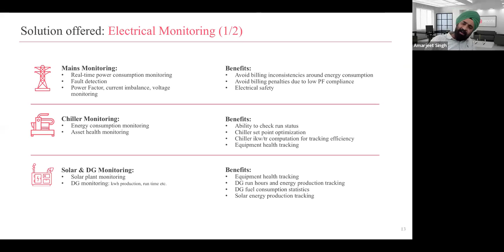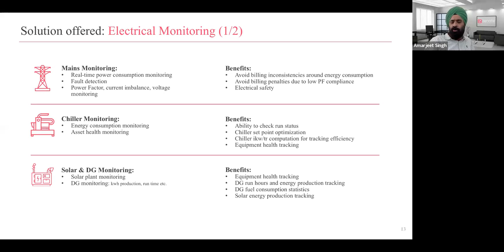Is your solar producing enough power given the weather conditions today? We were tracking that and raising alerts. We were telling them if there is potentially DG fuel pilferage, because whatever fuel they filled in, did they get enough units of consumption out of that or not? How many run hours did the DG operate at? Was it operating at the right capacity? You may have an over-provisioned or under-provisioned DG, etc. All of those things can now be provided from the data.